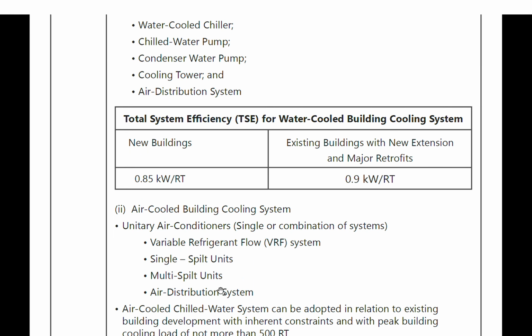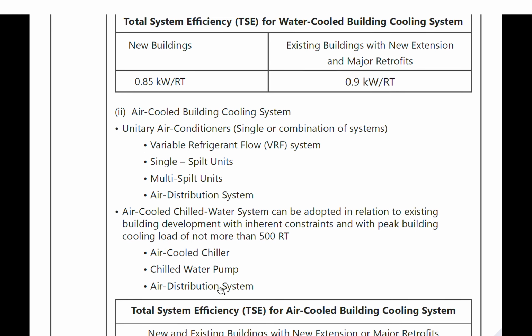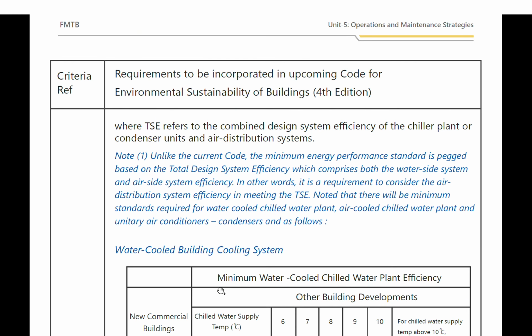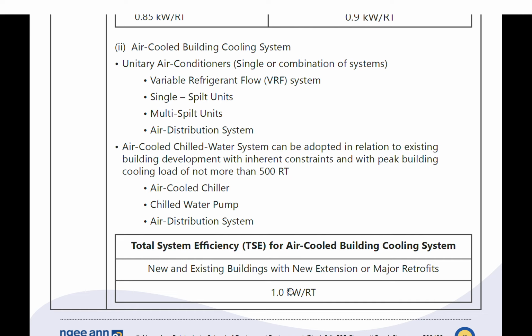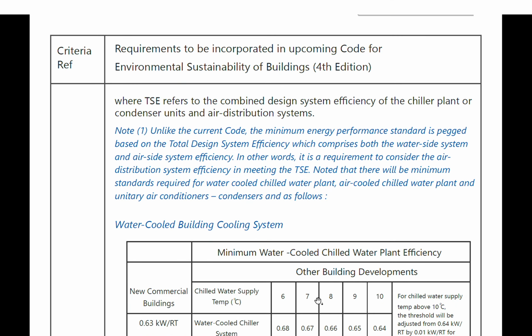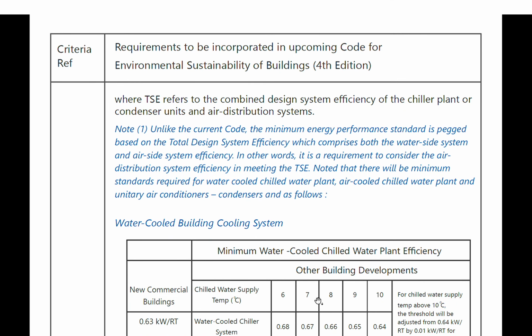So air cool is basically using air as a cooling media, right? As a cooling media, it reaches up to about 1.0 kilowatt per RT. So there's a significant difference between water cool and air cool. Learning this course, basically we know and understand what the kilowatt per RT is in terms of both chillers. So the TSE refers to the combination of design and chiller plant or condenser unit for air distribution.